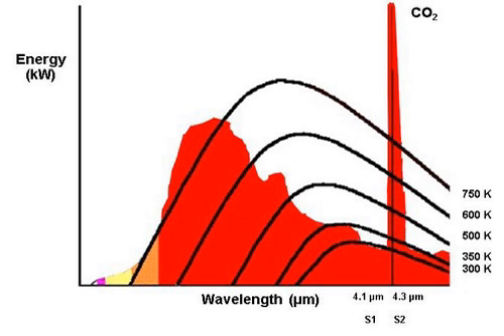Dual IR flame detection. Dual IR flame detectors compare the threshold signal in two infrared ranges. Often one sensor looks at the 4.4 micrometer carbon dioxide (CO2) band, while the other sensor looks at a reference frequency. Sensing the CO2 emission is appropriate for hydrocarbon fuels. For non-carbon-based fuels, e.g., hydrogen, the broadband water bands are sensed.